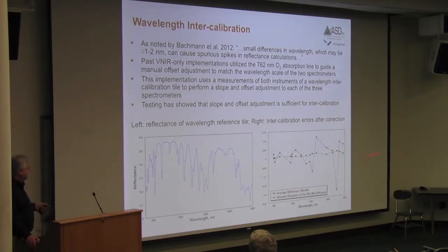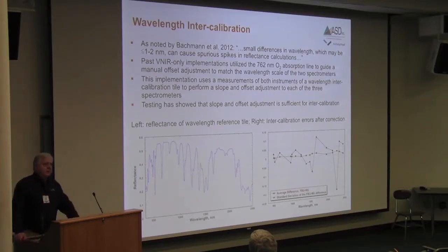We decided to use the slope and offset because back in 2007 we did an interesting experiment where we just put a spectrometer in the back of one of the employees' cars and drove it down these four-wheel drive dirt roads, and the whole idea was to let it bounce around a bit and see what the characteristics of the drift in wavelength calibration were on a typical instrument. And we found that a slope and offset was enough to correct for around 95% of the shift that we saw.